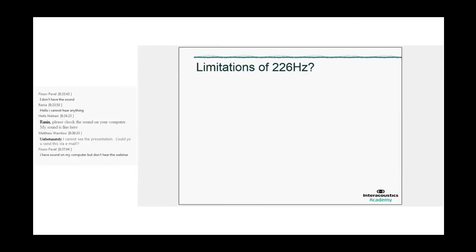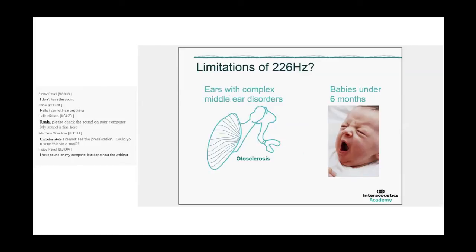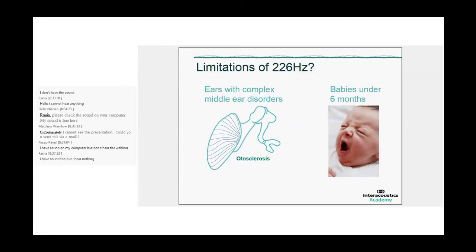So what are limitations of 226 hertz? First of all, if we test babies under 6 months, the problem is that with 226 hertz, we measure ear canal properties instead of the properties of the middle ear. And to overcome that, we can use 1000 hertz. And secondly, the 226 hertz probe tone doesn't really differentiate well for quite a lot of pathologies of the middle ear. This is just one example. If we look at otosclerosis, where there is a fixation of the stapes, then basically the tympanogram can look pretty normal. So limitation is basically that it doesn't differentiate very well with 226 hertz.